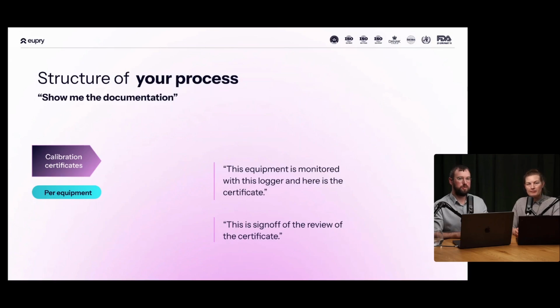So to sum up, what are the documents? Often we see a process description in which you identify what your process is, and that's often multi-equipment, multi-facility. So you get it in, it's intermediate storage, stored long-term in a fridge, then out of intermediate storage, and then outgoing. Then you start specifying what your equipment should do, both your fridge, for example, what it should be capable of doing, and so forth. Then you end up with the monitoring equipment and your calibration. There will also be some idea in looking into the allowances. You might have a facility or equipment that you allow to go out of temperature range for a certain amount of time, and that should be described as well, which is also valuable.